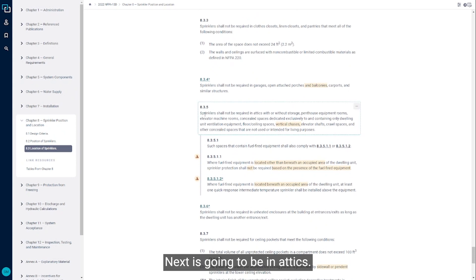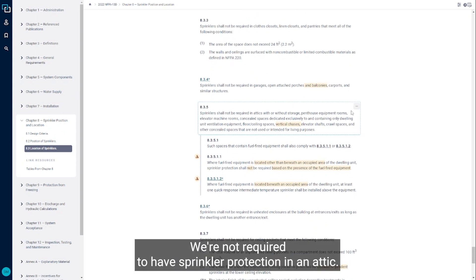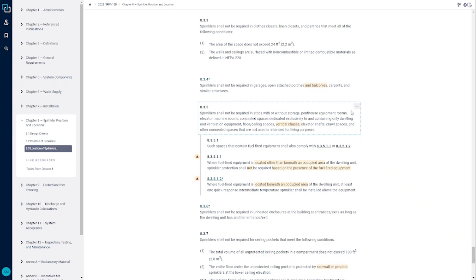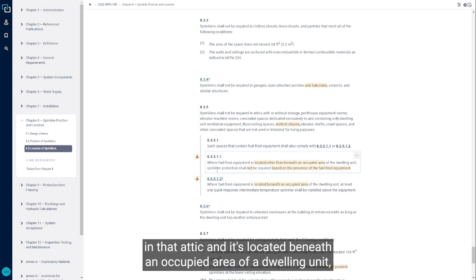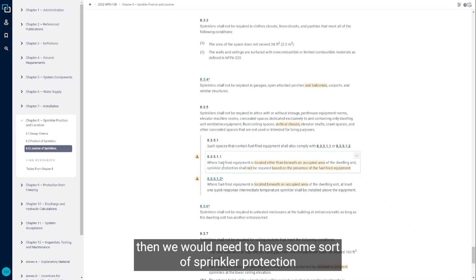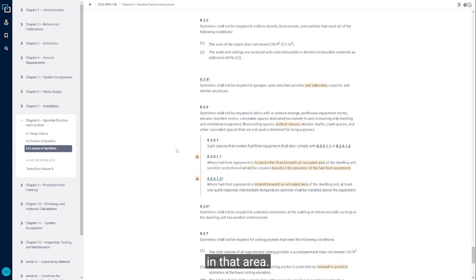Next is going to be attics. We're not required to have sprinkler protection in an attic. The only thing is if there were fuel fired equipment located in that attic and it's located beneath an occupied area of a dwelling unit, then we would need to have some sort of sprinkler protection in that area.